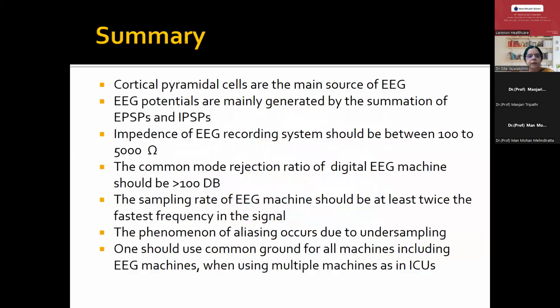So to summarize, the cortical pyramidal cells are the main source of EEG activity. The EEG potentials are generated by the summation of excitatory postsynaptic potentials and inhibitory postsynaptic potentials. The impedance of the EEG recording machine should be between 100 and 5,000 ohms. One should know the common mode rejection ratio of the digital EEG machine, which should be more than 100 decibels. The sampling rate of the EEG machine should be at least twice the fastest frequency of the signal, that is 70 hertz. So it should be more than 140, but nowadays we get more than 210.